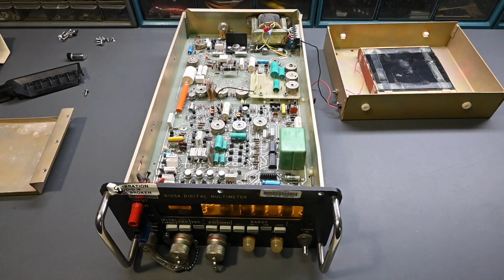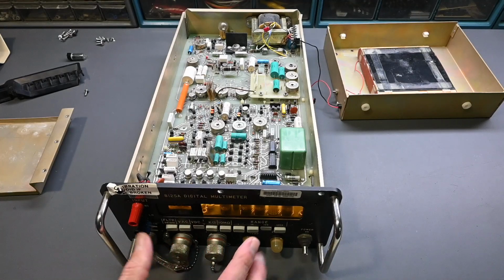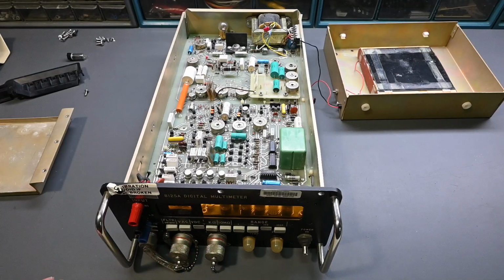The other thing I'm noticing is that these fuse holders are broken. Unfortunately, they're not just loose, they're actually cracked, the housing is cracked on them. But I think I can power up the instrument because the break is such that electrically they should still work, though they'll need to be replaced. It may not be the easiest thing to replace, I might have to pull this whole front panel off. I'll have to look closer. That's unfortunate that both of those are broken.